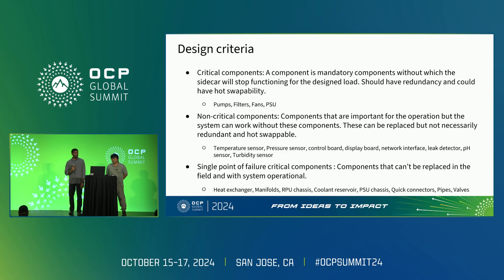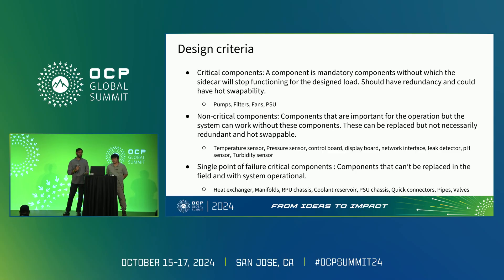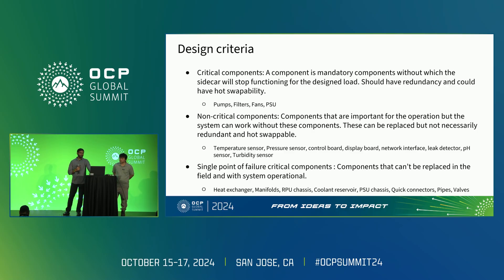Single point of failure components include the heat exchanger itself, manifolds, tubes, and valves. Without these, you would not be able to operate the sidecar at all — this would represent a complete failure of that particular sidecar. We are defining this criteria as a guideline so all vendors can unify on sidecar component design.